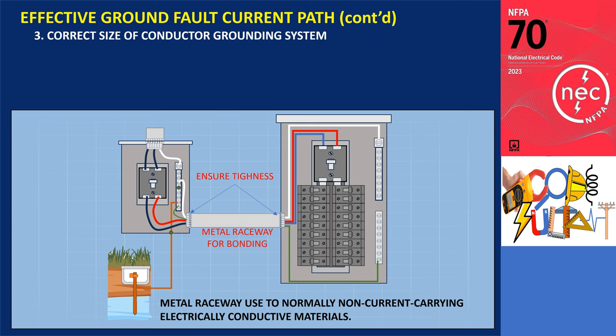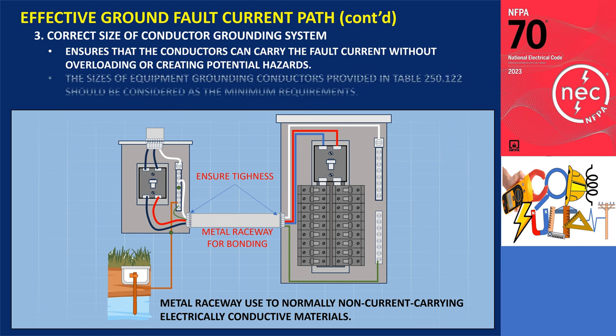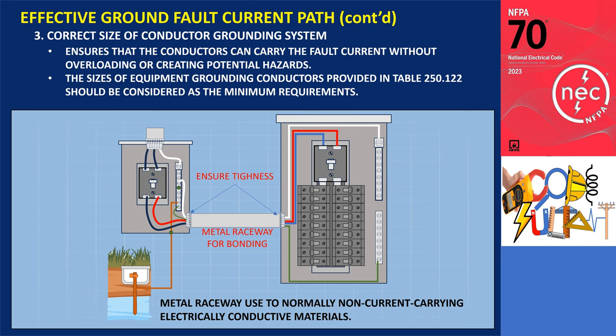Using properly sized conductors is crucial to safely handle the maximum expected fault current, ensuring they can carry fault current without overloading or creating potential hazards. The minimum sizes for grounded conductors, bonding conductors, and equipment grounding conductors can be found in Article 250. The sizes of equipment grounding conductors in Table 250.122 should be considered the minimum requirements, and using conductors that meet or exceed these sizes ensures safety and effectiveness of the grounding and bonding system.